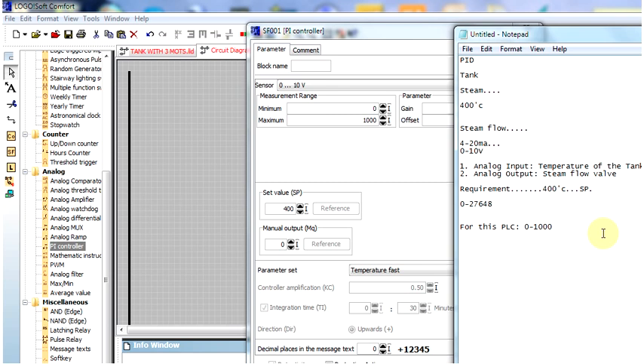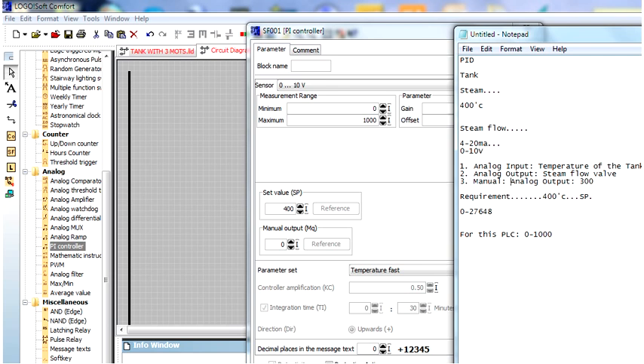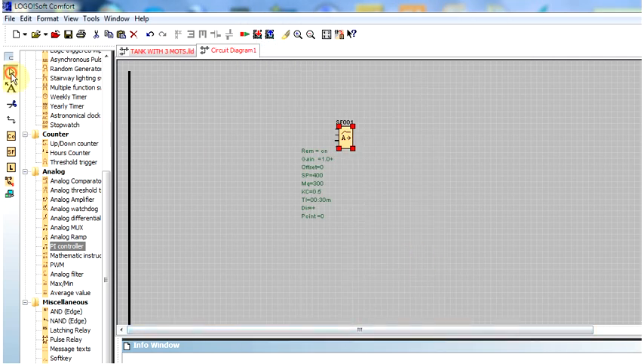The output will control the steam flow valve automatically. But if I want to apply a manual system, a fixed control value will go to the analog output. For this, I can fix the analog output to, say, 300. We know that if we supply 300 the temperature will be approximately 400. This is not required by the PID controller, but I keep it as a manual value — when you design an automation system you must keep a manual option in case the automatic system does not work properly.